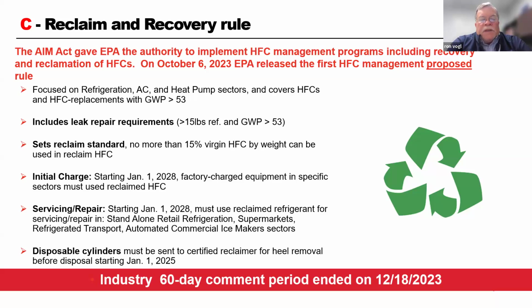And the last one, they are trying to make disposable returnables, frankly, not disposable any longer. You'd have to bring your disposable cylinder back to Johnstone. They would have to package it up and then send it to a reclaimer to pull out any what we call residual refrigerant or a heel. The issue I have with that is under 608, prior to disposing of a cylinder, you're supposed to be pulling that to subatmospheric and recovering everything now.